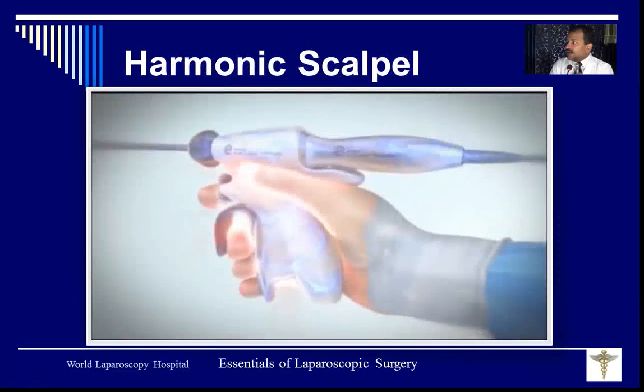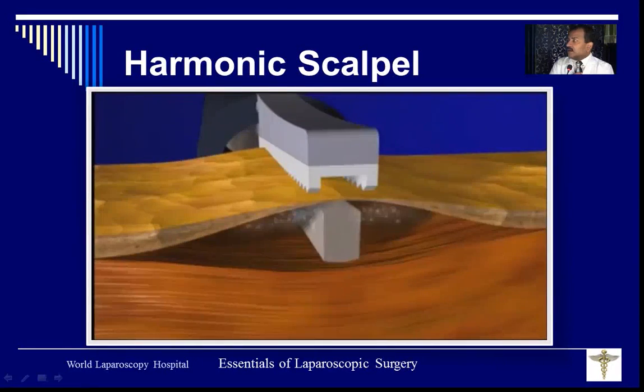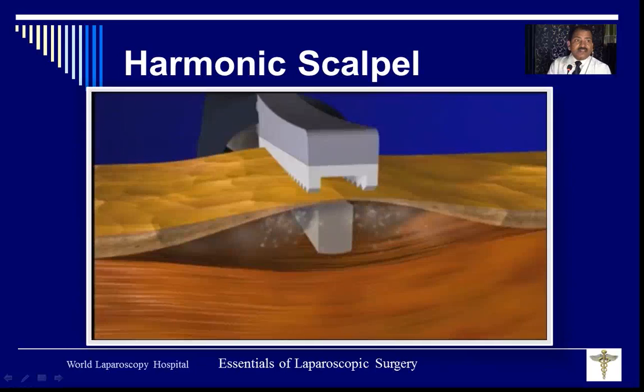And then you have control with your finger, and you can work. This is the vibration. Do you know this vibration is visible? Just to show you, but in reality, it will not be visible. It vibrates. So these are the hook, harmonic hook. You can attach it here, and then you can do cholecystectomy, you can do colpotomy, you can do any surgery, and the tip vibrates. Then you can use harmonic ace. This is harmonic ace. You can use it even in open surgery, and it has two jaws. If you see, the upper jaw has silicon, and actually the lower jaw vibrates like that. You are seeing it, but here you cannot see.